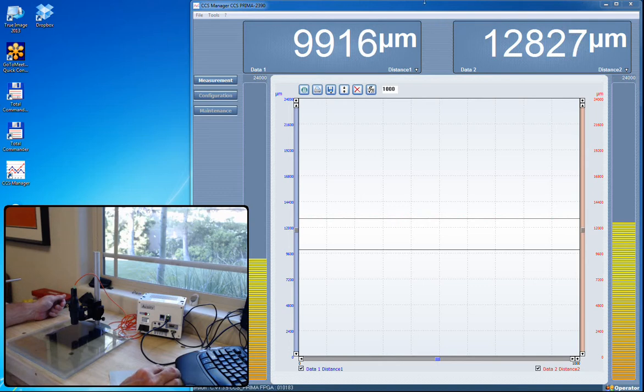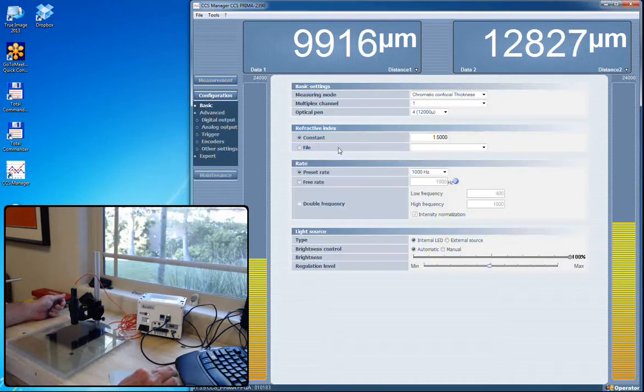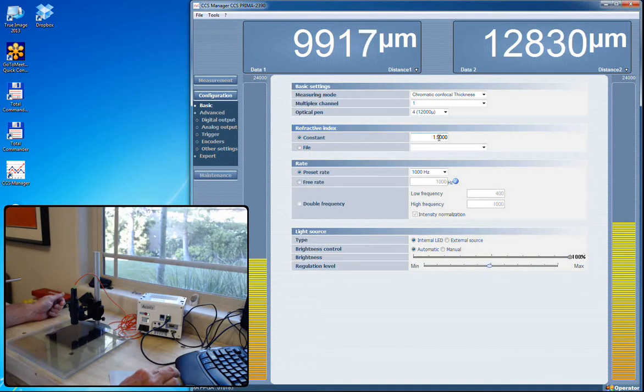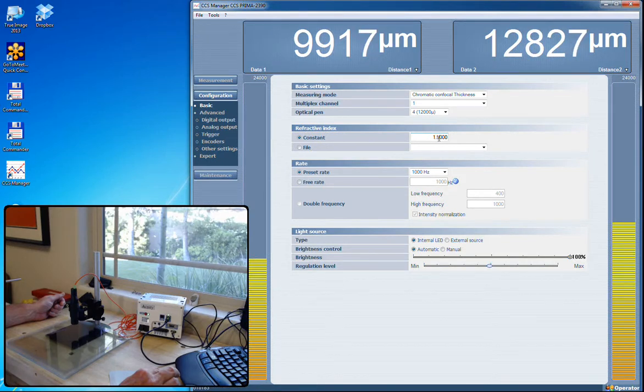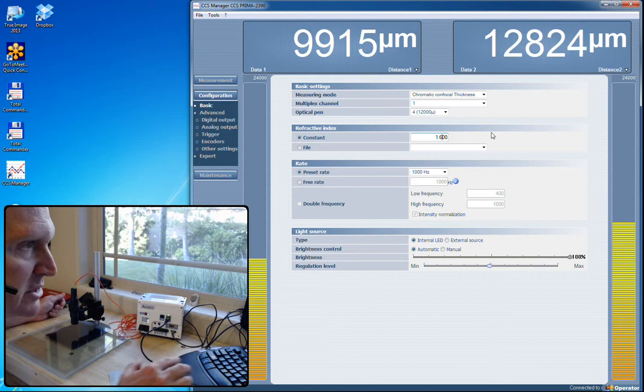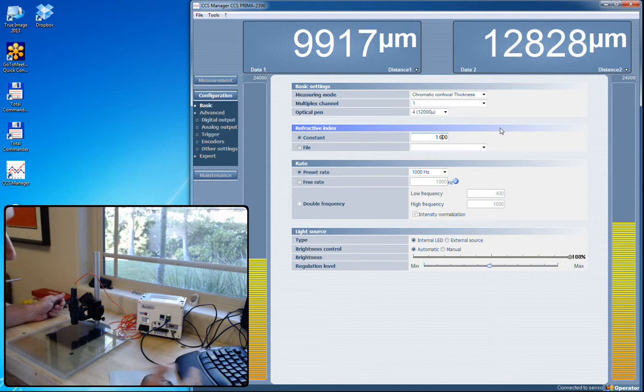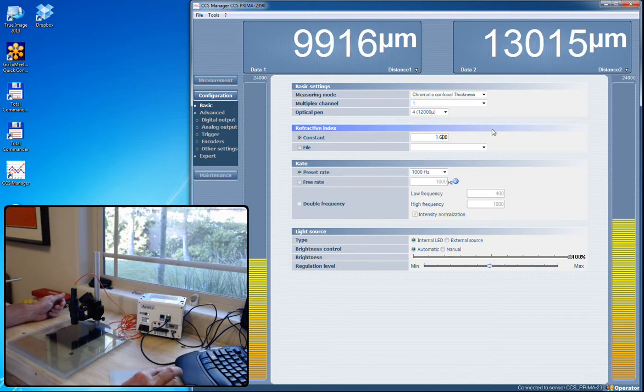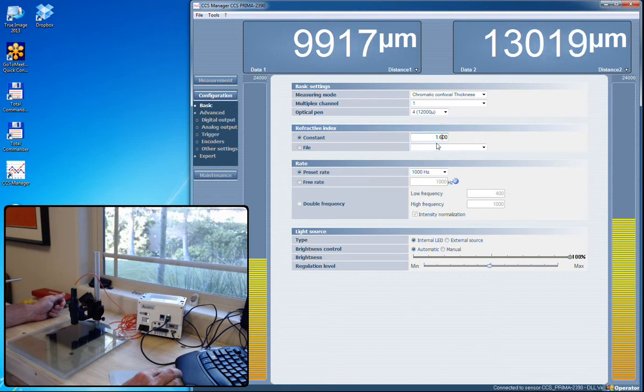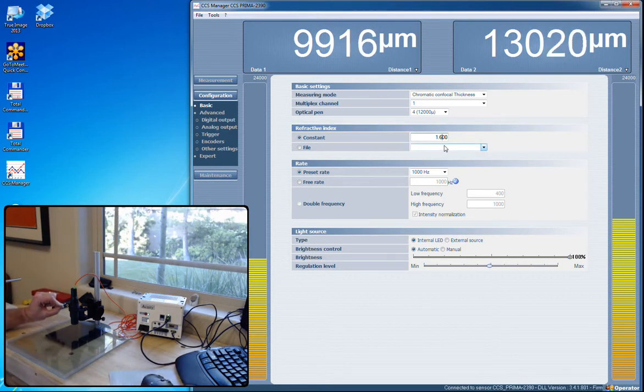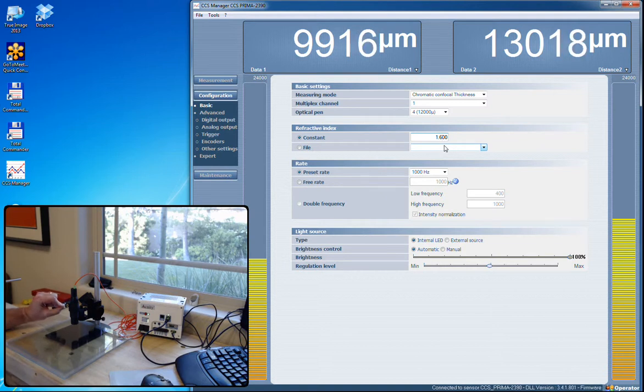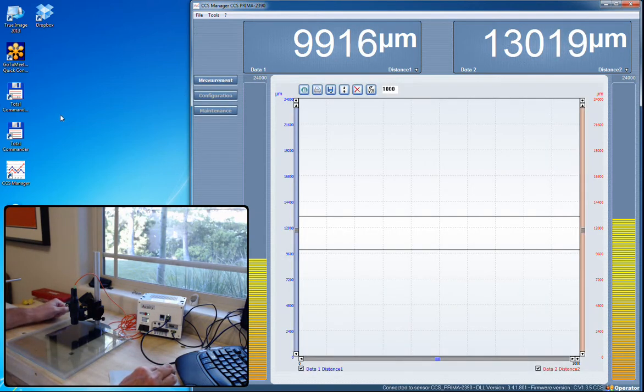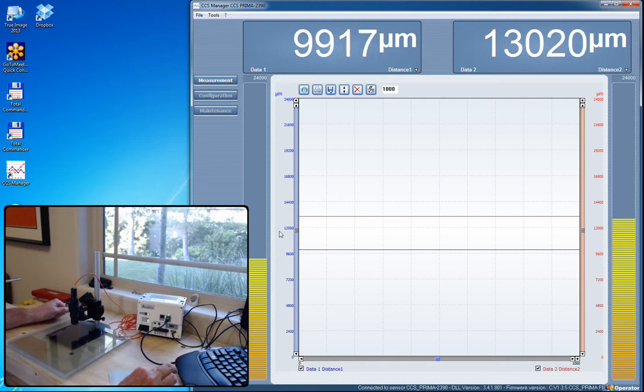We can make this configuration change where we have an option to put an index of refraction. We can change that and glass may be closer to 1.6, and we input that in there and you'll see that change happen right away. Based upon that, changing the index of refraction, we can take a known sample and very accurately calculate that index of refraction.